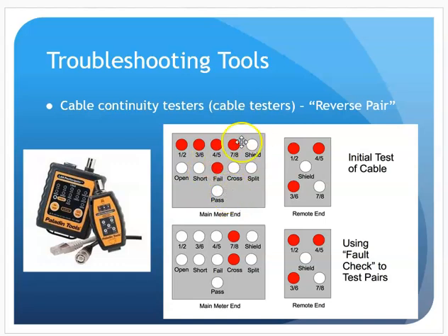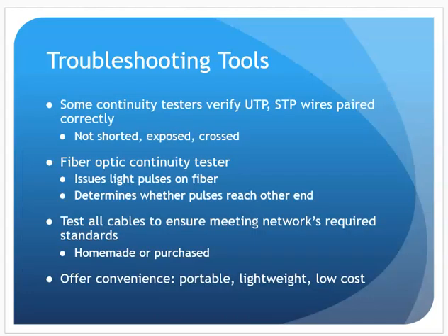When I do this, again, it'll show a fail. I go through the fault check. It'll let me know what wire pair is crossed or they're flipped over. This tends to happen when you do patch cables. Slide those wires in the connector, they tend to flip-flop on you, and I get the brown, white brown instead of the white brown, brown. And it'll show me that wire pair is reversed, and I would need to re-terminate that end. I'd find the end that needs to be re-terminated.